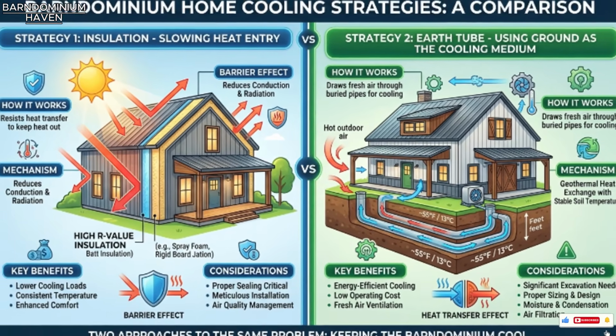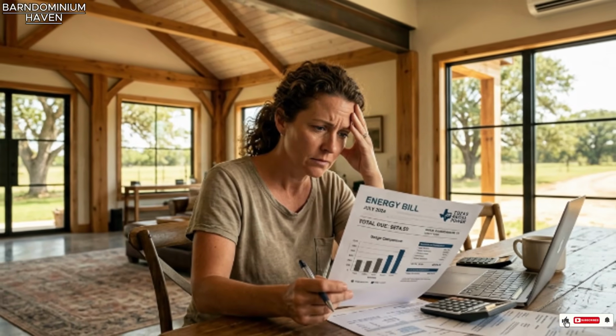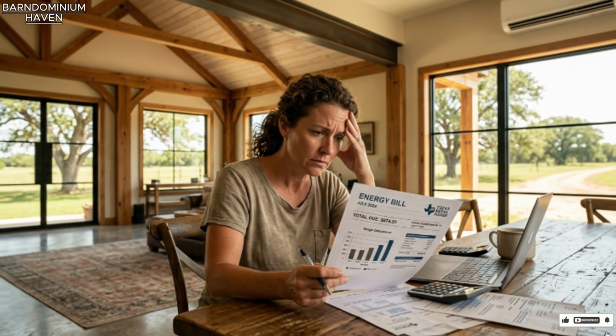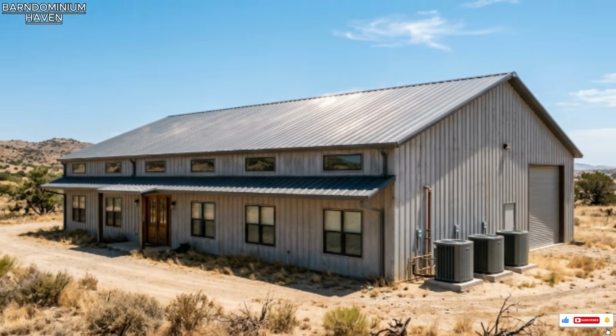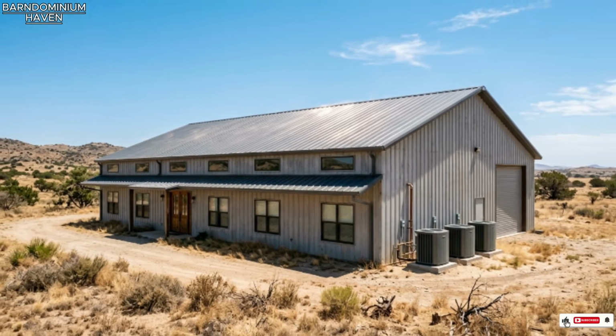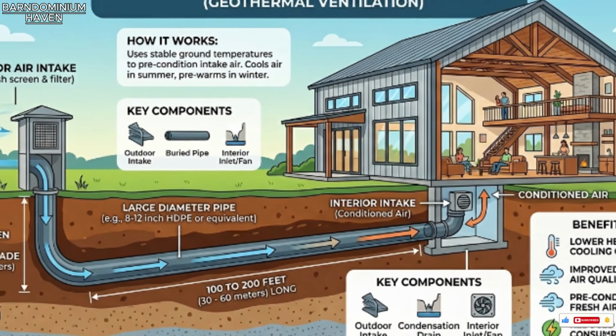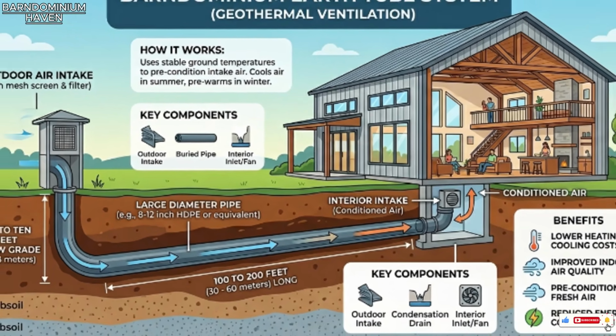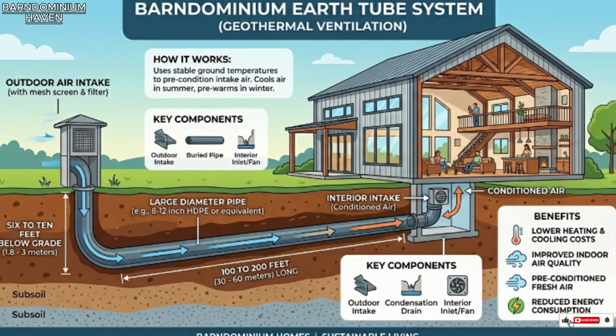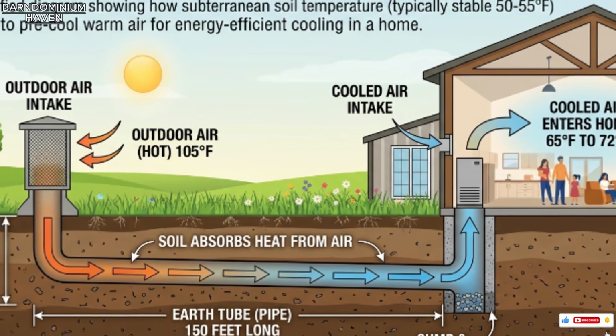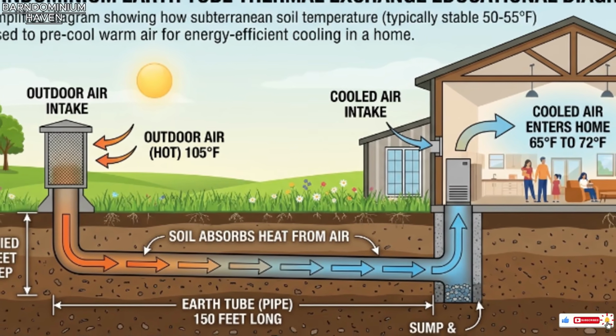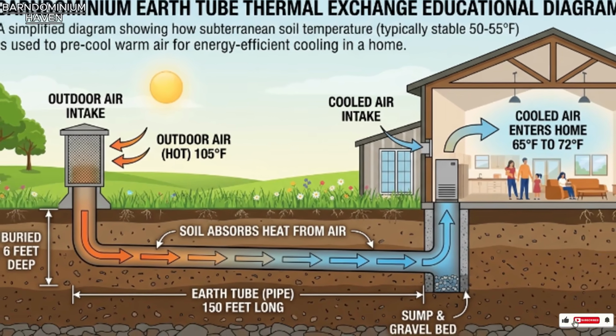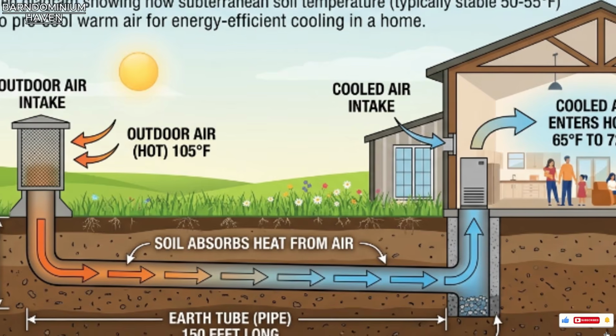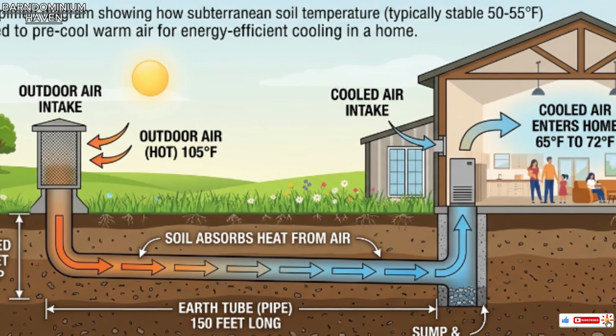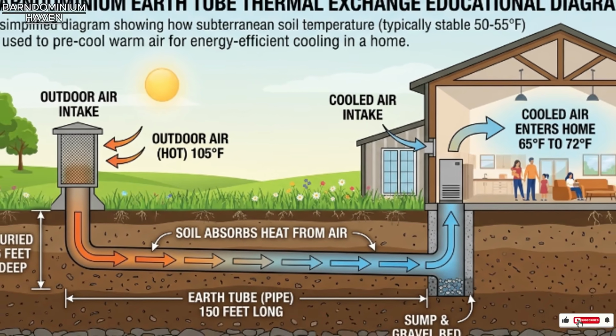The solution that the barndominium community has not broadly adopted is to stop fighting the ambient air and start using the ambient ground instead. Earth tubes, also called earth-air heat exchangers, ground-coupled air systems, or Canadian wells in some European building traditions, are large-diameter pipes buried at a depth of 6 to 10 feet below grade, through which outdoor air is drawn before entering the building's ventilation system.